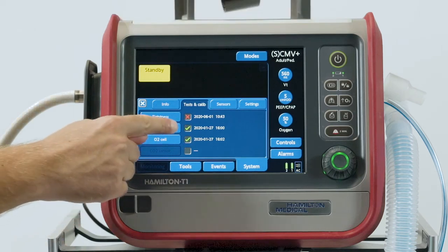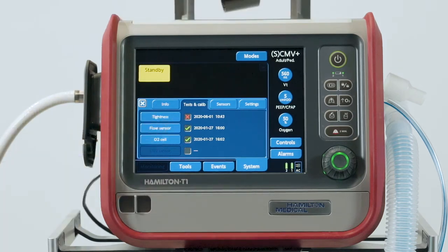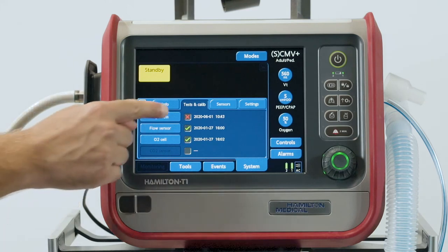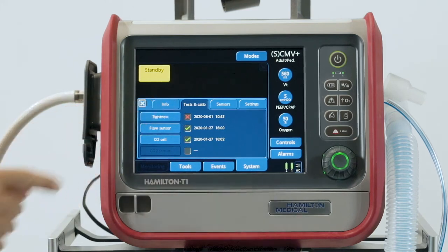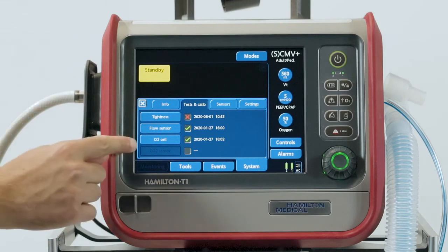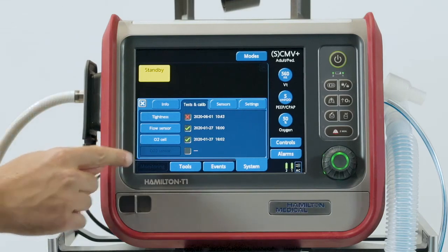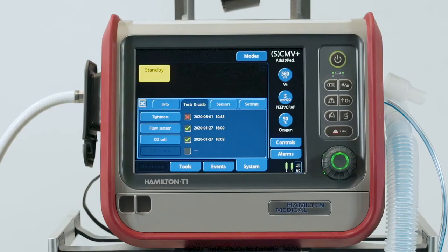A green check mark tells you the component is calibrated and ready, while a red X shows you that the last calibration was not successful. If you see an empty box, this means that the test or calibration has not been carried out. If CO2 monitoring is not enabled, the box will be grayed out. Make sure you do a tightness test and calibrate the flow sensor each time you've connected a new breathing circuit or component, including a flow sensor.